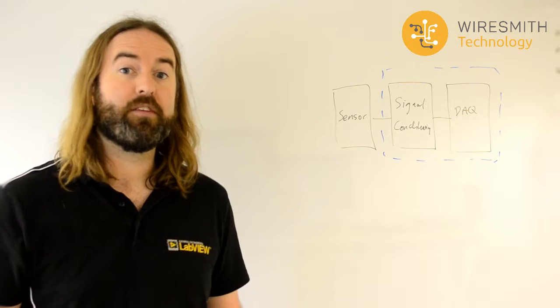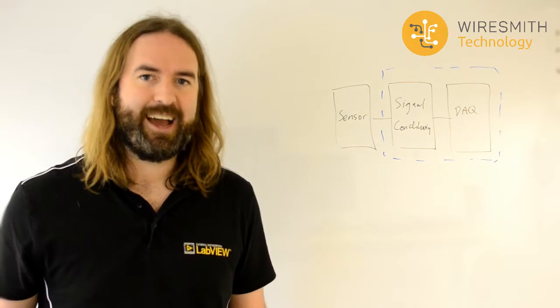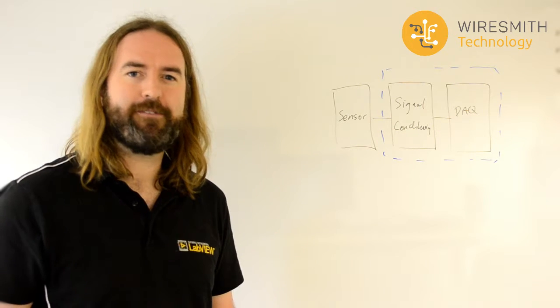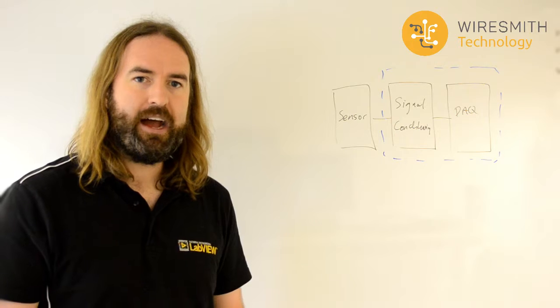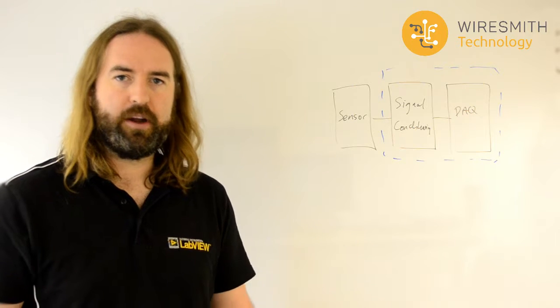There are problems with it and costs associated with it. So obviously you have to have the calibrator hardware. You need something that can generate these signals about 4 to 10 times more accurate than what you're trying to measure. And depending on those signals, that can become very expensive to set up. You need operators that can run the calibration, obviously that's going to take their time as well.